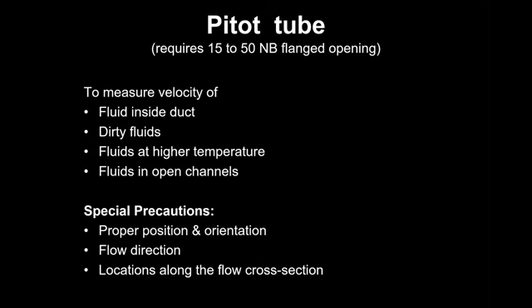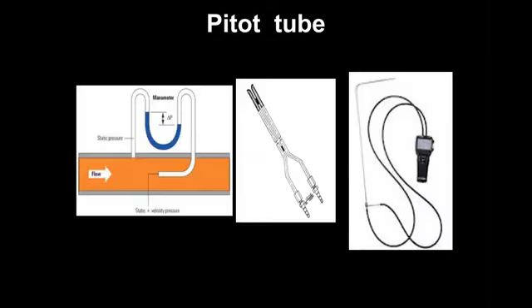It can be used for dirty fluids. The other two cannot be used. It can also be used for fluids in open channel. It's a separate topic. We don't normally come across it in audit. The precautions are on the same lines. And there are typically 2 types of pitot tube. One is the S type, that is used for a dirty fluid, and the L type, that is used for clean fluids. So this is the S type pitot tube, where the openings are on the larger side.